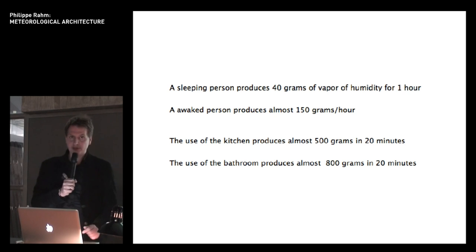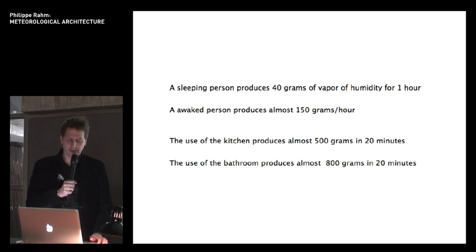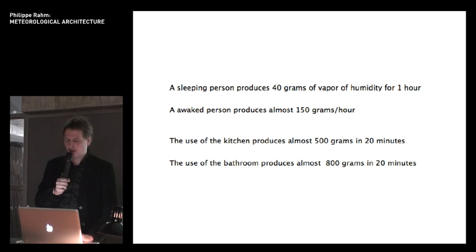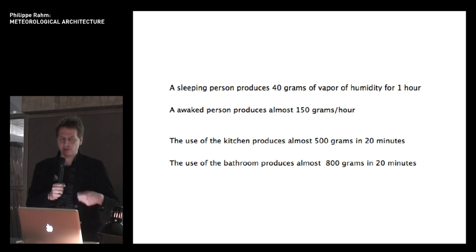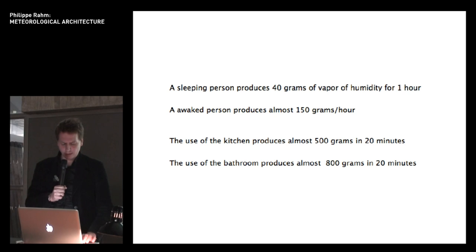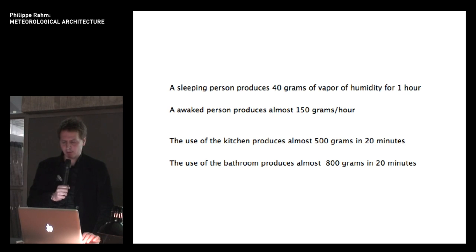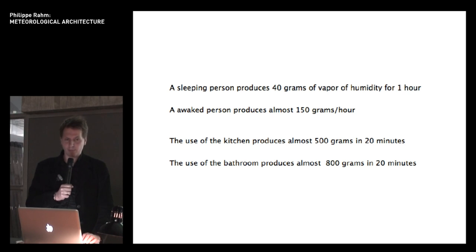Focusing on vapor in the building, if you are asleep you produce 40 grams of vapor per hour. In a normal position, 150 grams per hour. Cooking in the kitchen can produce 500 grams in 20 minutes. Taking a shower produces 800 grams in 20 minutes. So, related to the use of space, you produce different quantities of vapor inside the space.